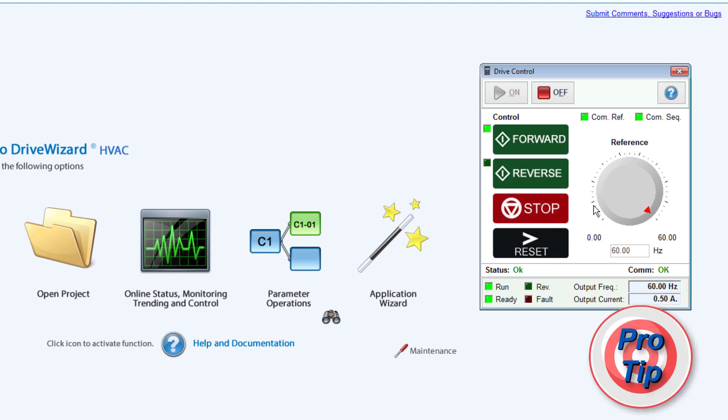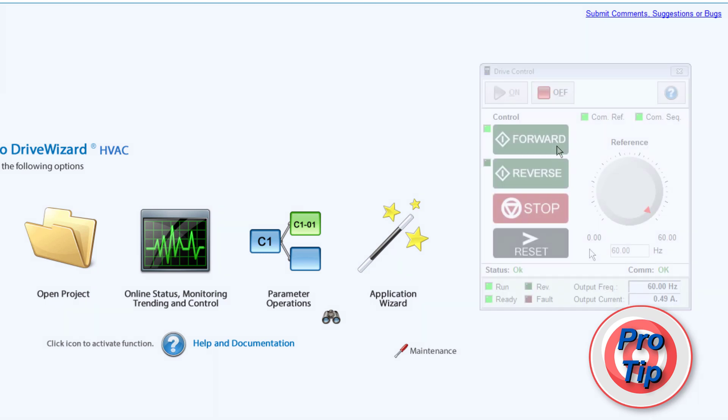Pro tip: By default, closing the drive control window does not stop the drive. Once again, to properly stop the drive, click the Stop button and then the Off button to turn off communication control.